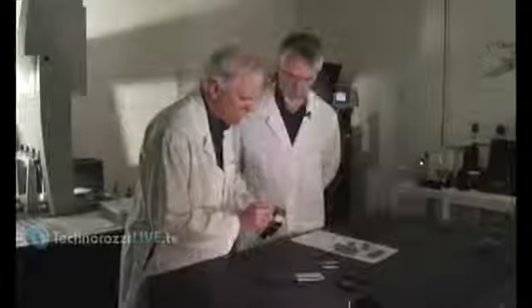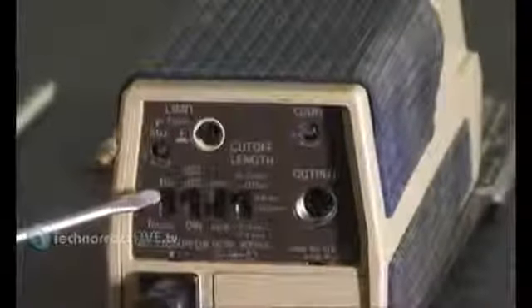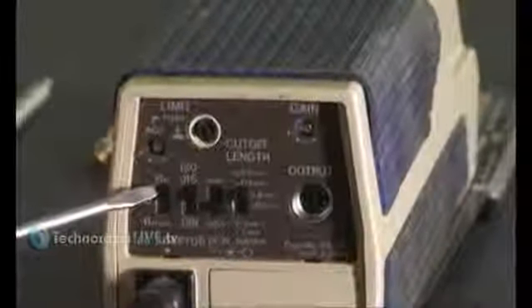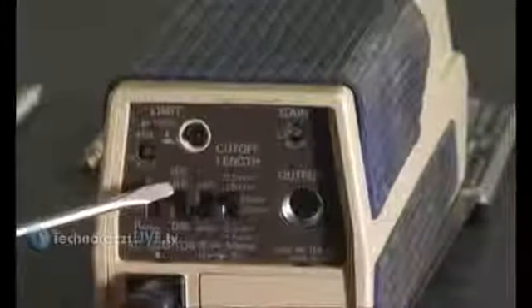Now there are several things to consider when you're setting up, and they're found on the back of this unit. The first one is, what are you measuring? RA, RZ, or R max is what the choices are in this. Typically RA is what is used. Then are you using the ISO JIS specs or using DIN, which is a German spec? Typically it's the ISO JIS. And do you want your readouts to be in millimeters or in inches? We use inch. It can be either direction.